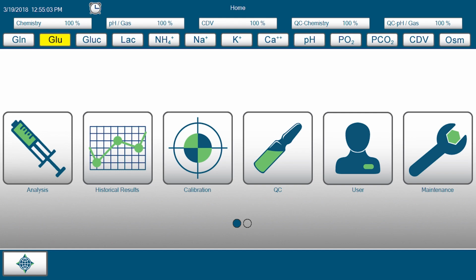For the osmometer module, the Osmo status icon will turn yellow when the number of clean tubes remaining in the osmometer turntable reaches less than 3, or when the osmometer calibration is within 3 days of expiring. Parameters in alert status are still available for testing and will still produce results, but the alert indicates that intervention will be required soon.